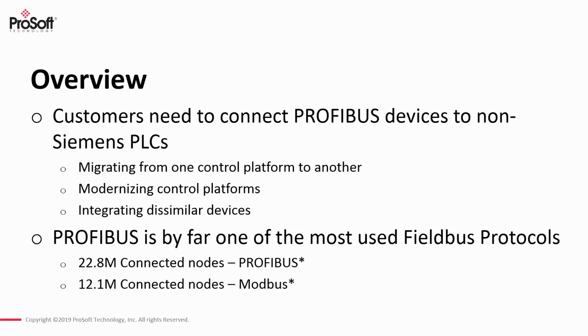A lot of times it's really about integrating dissimilar devices. You've got devices from various vendors throughout the world, and you want to bring that information into either a Rockwell PLC or some other vendor's PLC over EtherNet/IP, and really you need a protocol communication gateway.